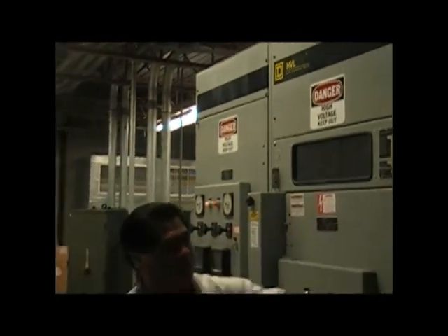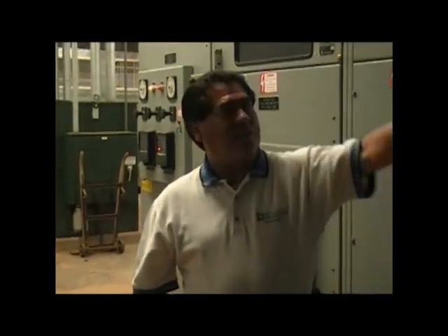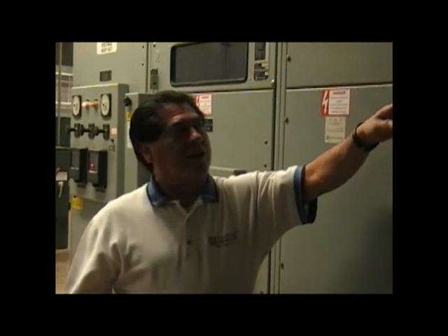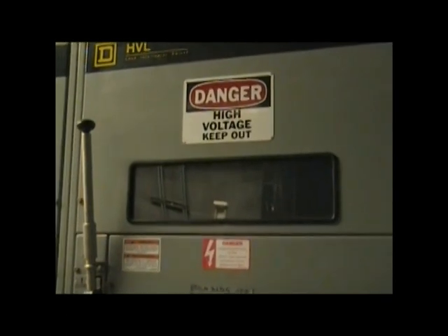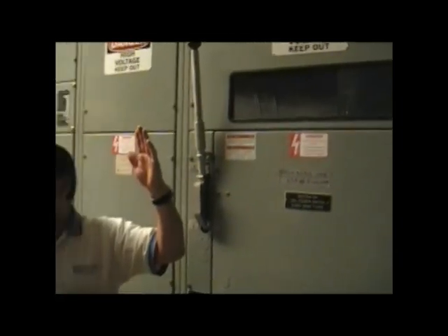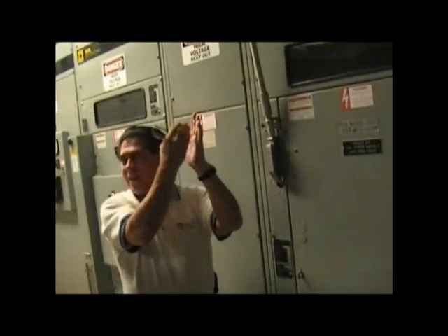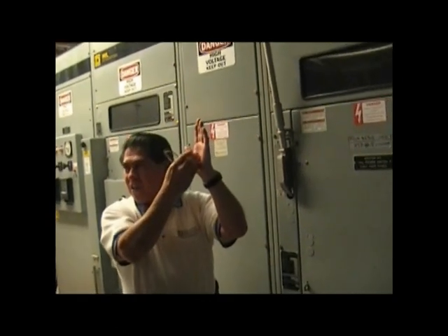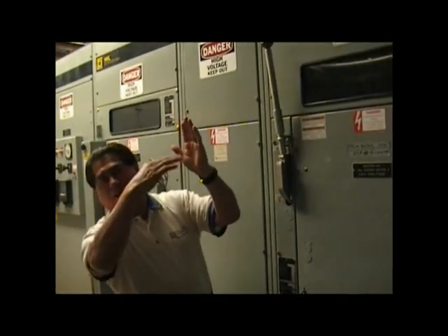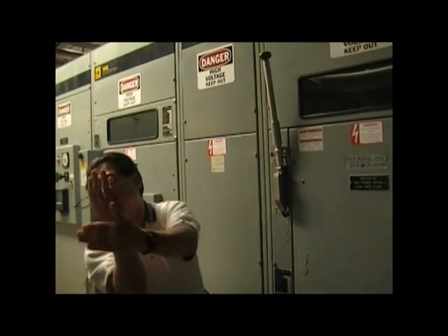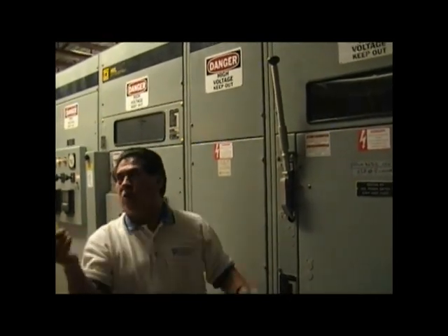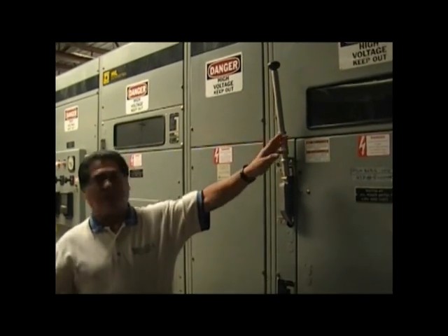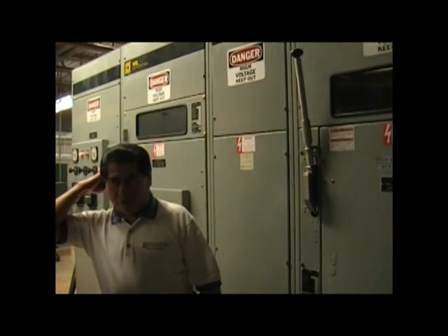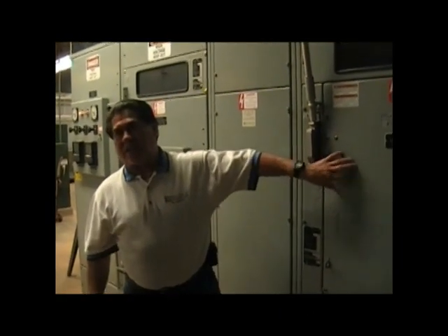This one's a little different, it's cut and dry. Just pull the handle down, and you can see the blade and everything else disconnect. See those arc chutes? There's a blade that's spring loaded and stays in contact until the main contact clears far enough to stop arcing, then it snaps out quickly, so there's no arc between the main and stationary blade, the actual moving blade. We didn't cover that before, but it's very cut and dry.